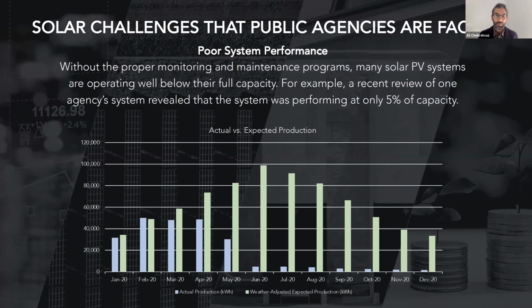In many cases, these systems produce a lot more noise than signal, and figuring out what's going on tends to be a challenge. The easy part is if the system fully trips and there's no production during the day, that sends a signal and folks realize something is going on and have to fix it. The quieter issue is underperformance, where the system is producing something, it's not completely out, so no major alarm goes out, it's just underperformance. Unless somebody's paying attention to the system and evaluating whether, given the solar irradiance available that day, the system is producing as much as it should, and whether that delta is acceptable, these issues can go unnoticed for a very long time.